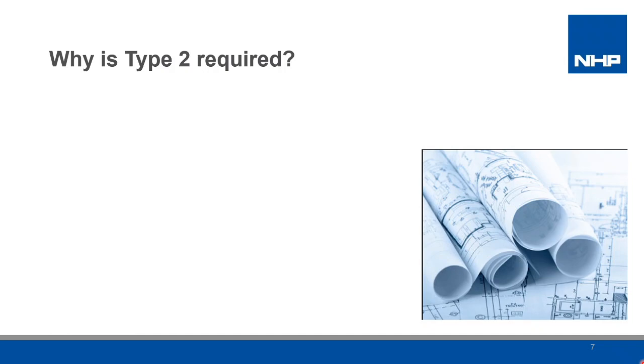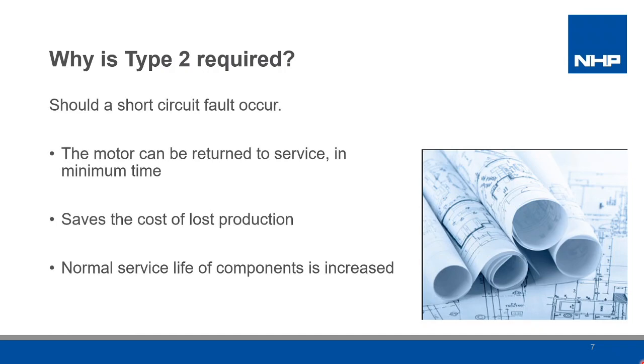So why do we have Type 2? Whilst the initial cost of a Type 2 combination will be slightly more than a Type 1, it is a cost of lost production. Should a short circuit fault occur at the site, it is a consideration for the end users. A Type 2 combination will allow for the motor starter to be returned to service quicker, as replacement of components is not required.